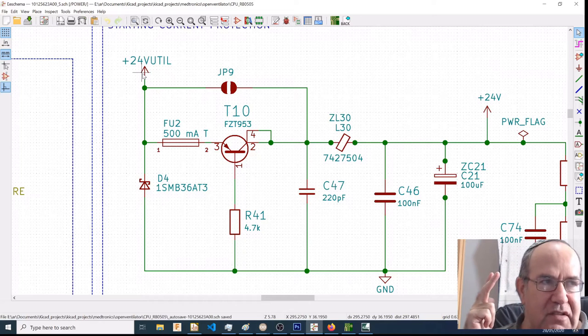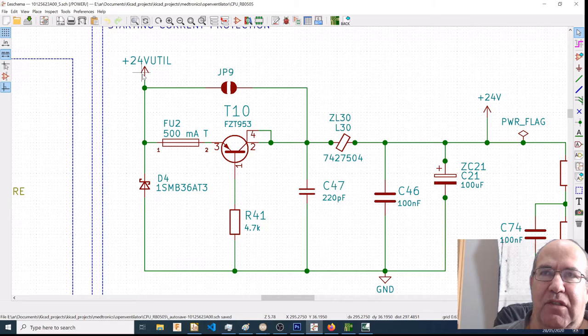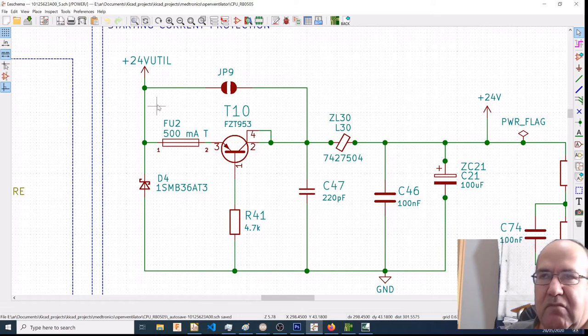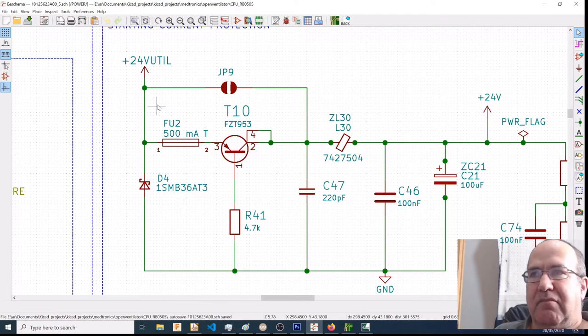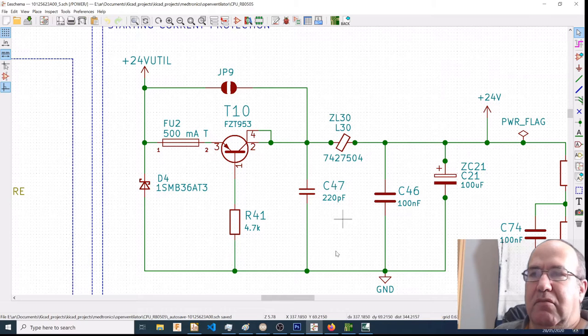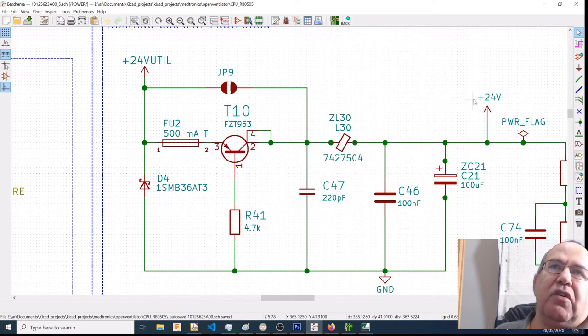A solenoid isn't a device which is going to worry about regulation. So to take it off before the fuse is not a bad idea, and that way, instead of having your 24 volt coming off the fused line, it's coming off the 24 volt util.